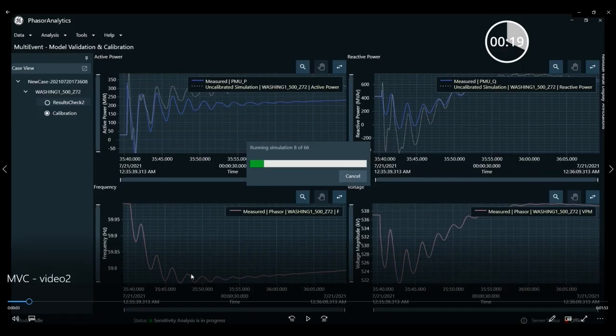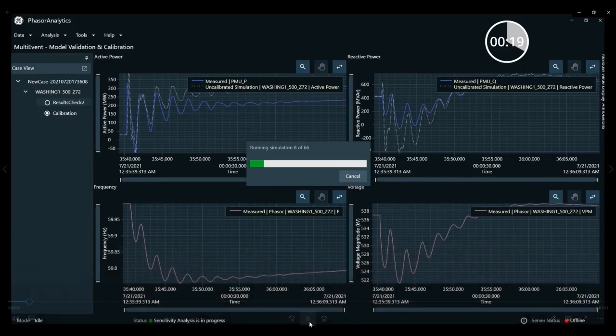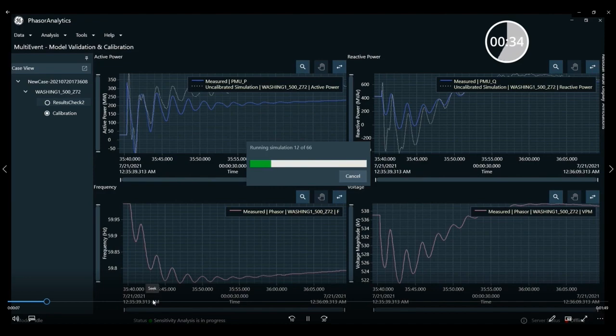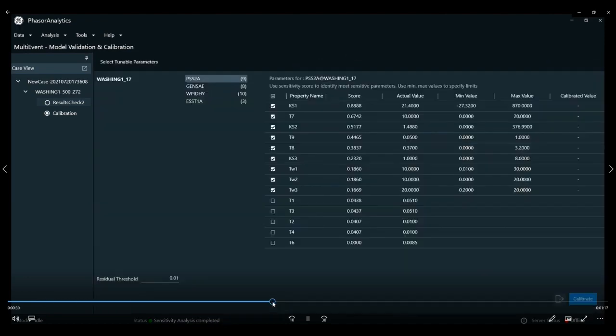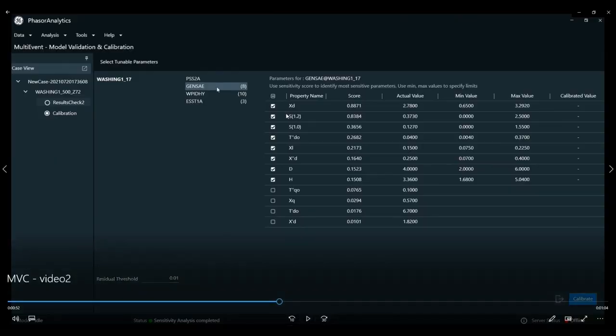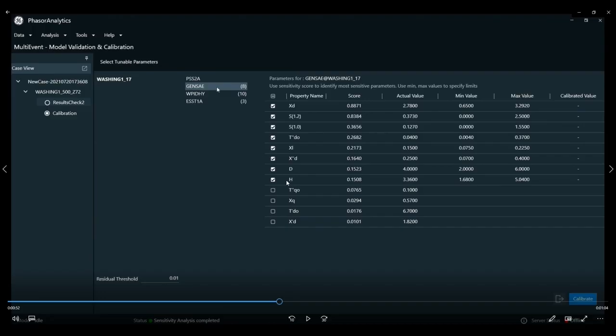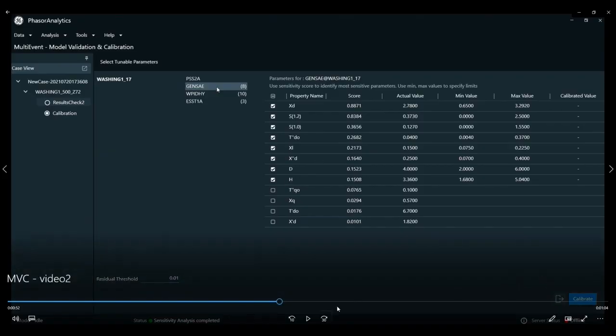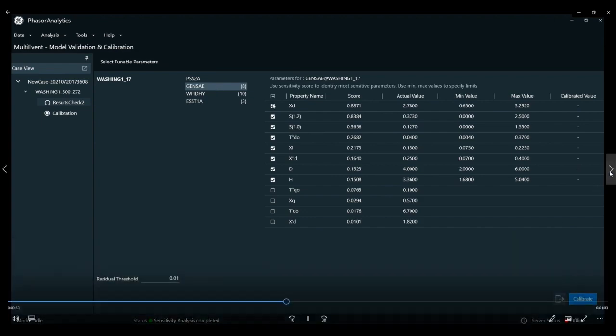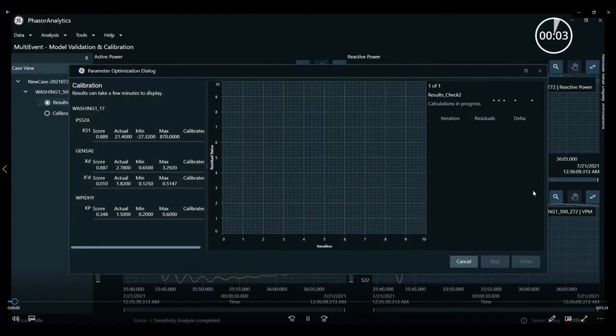So then we go on to the next step. And what we're doing here is a sensitivity analysis, where we are looking at what parameters are observable. And it comes back and tells you the set of parameters that it thinks we can calibrate, the ones that are checked. There are minimum and maximum ranges for these parameters as it goes through the optimization to calibrate it. And we have different elements of the dynamic model. So we have the power system stabilizer, we've got the governor model, etc. And then when you click on the calibrate button, it then goes onto the calibration.